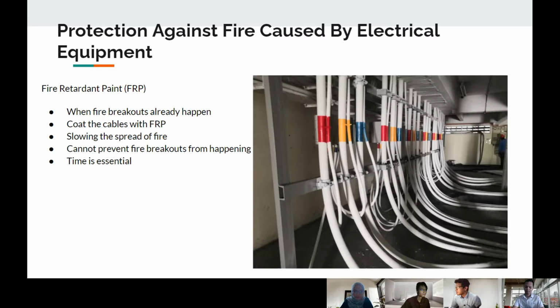Lastly, the fire retardant paint. Fire retardant paint is a coating that is used to coat the cables inside a building. This type of protection is used when the fire breakout has already happened. This method can prevent fire from spreading and damaging other appliances, which may lead to a serious problem. However, FRP is a substance that is used to slow or stop the spread of fire by reducing its intensity, and it cannot prevent fire breakouts from happening. The concept is using a chemical reaction that reduces the flammability of fuels or delays their combustion.